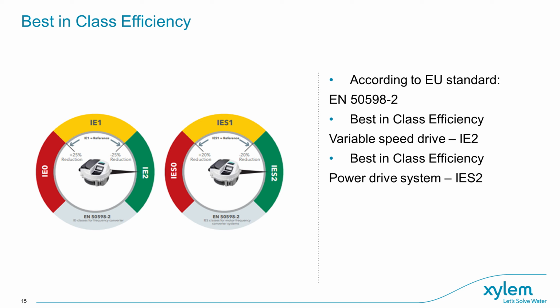With the standard now in place, the Hydrovar has the highest possible IE rating of IE2, and when fitted to a Lowara motor, has the highest IES rating of IES2. So the installer can be sure that if they fit a GHVR booster set, they are installing a set with the best-in-class inverter efficiency.